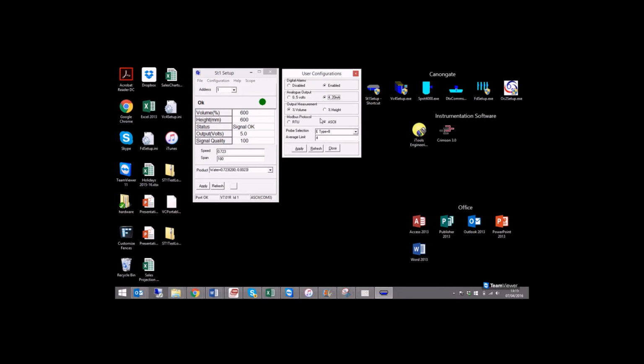And Modbus protocol we already spoke about - that might need to change in order to connect the instrument to your computer. Finally, probe selection: there's a letter on the back of each probe indicating probe thickness, and this should be matched for ideal operation. If you don't, it might work, but this should be changed to match whatever probe you're using on the test cell.